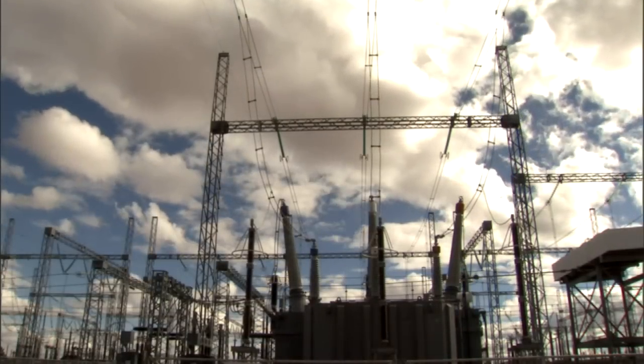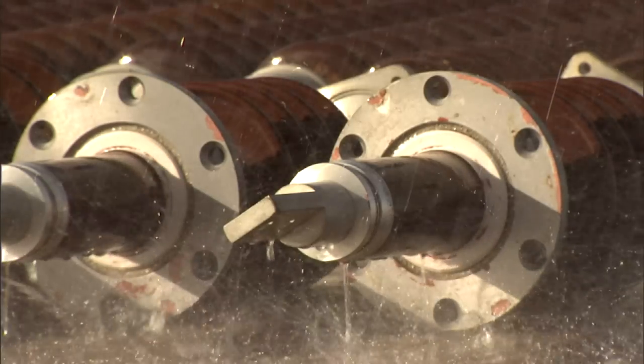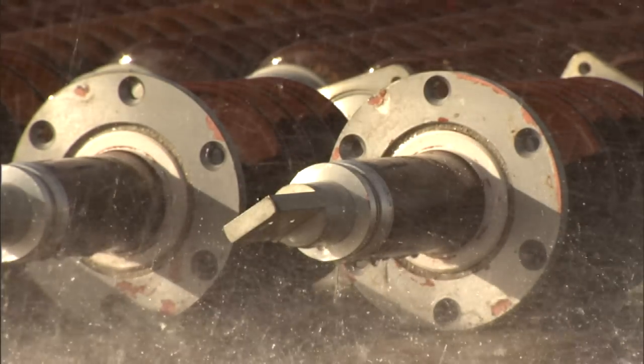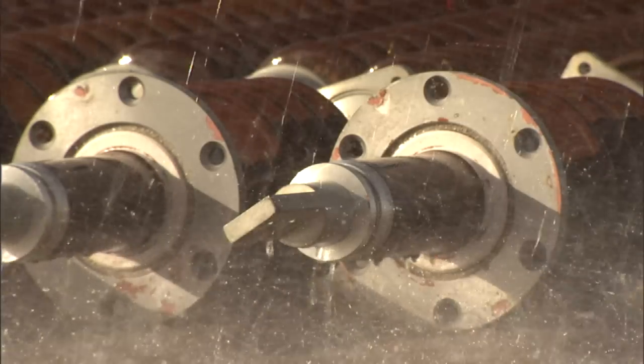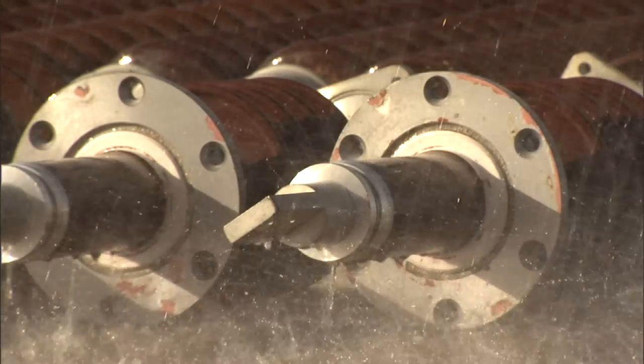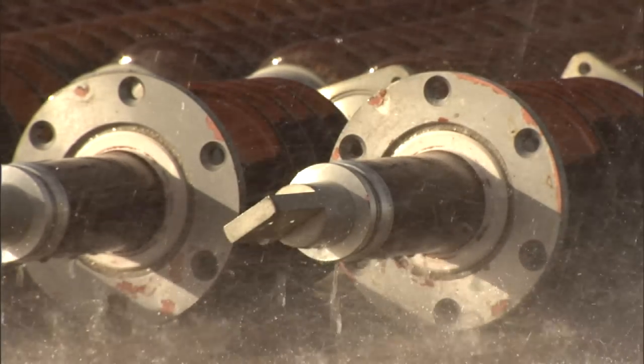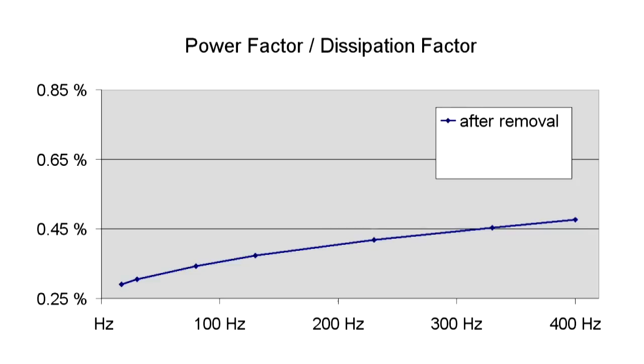Humidity has a lot of influence on the dissipation factor or the power factor. This 220 kV resin impregnated bushing was stored outdoors without any protective measures. The active part did not rest sealed under oil as would be the case within a transformer. Immediately after removing it from the transformer, the initial curve was recorded. Three months later, another measurement was made, and no minimum is now visible, with a generally higher level.